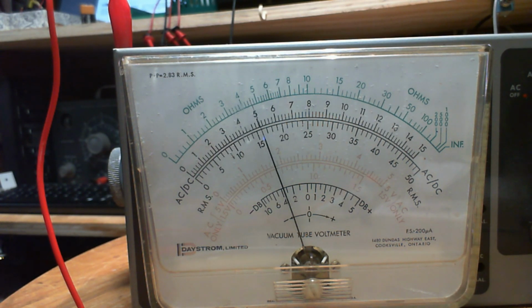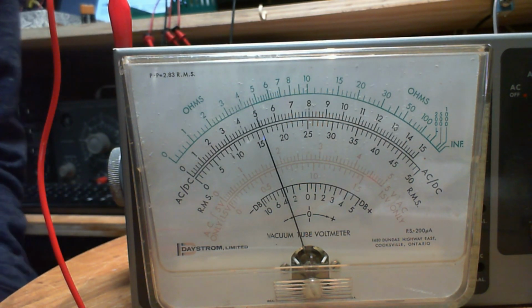Let's see what it says. Recommended that the tubes be aged before final calibration, accomplished by keeping the instrument turned on for 2 days. Final calibration should be done the same way as initial calibration, careful calibration, AC standard, blah, blah, blah. Oh, hello, Peanut. Preferably, use a voltage near full scale on the VTVM, for instance, 140 volts or 40 volts or blah, blah, blah. So I was kind of shooting towards the middle of the scale rather than the high end, but I'm sure everything is just fine. And hey, there's a whole bunch of stuff here on the combination probe. So I'm going to read up this manual completely. And great, I think it's great.